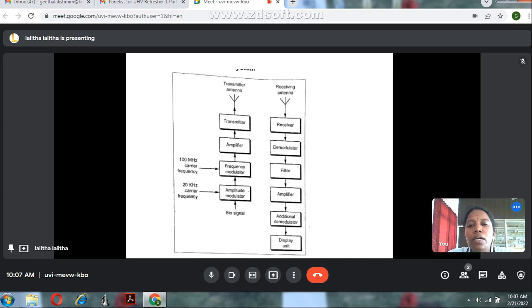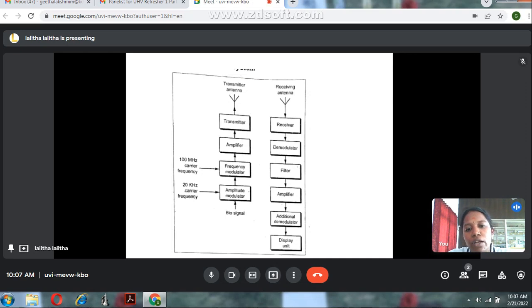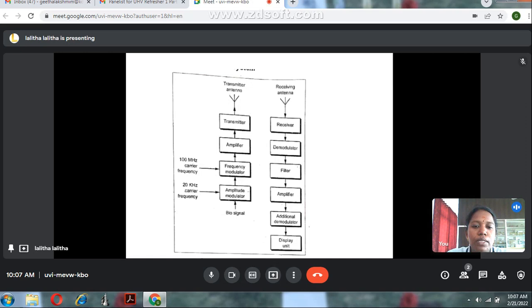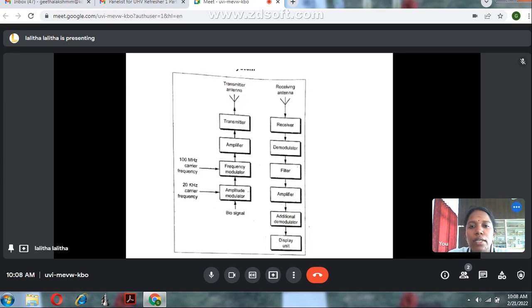On the receiver side, the receiving antenna receives the signal from the transmitting antenna. The received signal is connected to a demodulator, which demodulates the signal. The demodulator output is connected to a filter, which removes unwanted signals. The filtered signal goes to an amplifier to boost weak signals, then to an additional demodulator, which produces the output displayed on the display unit as the original biological signal.